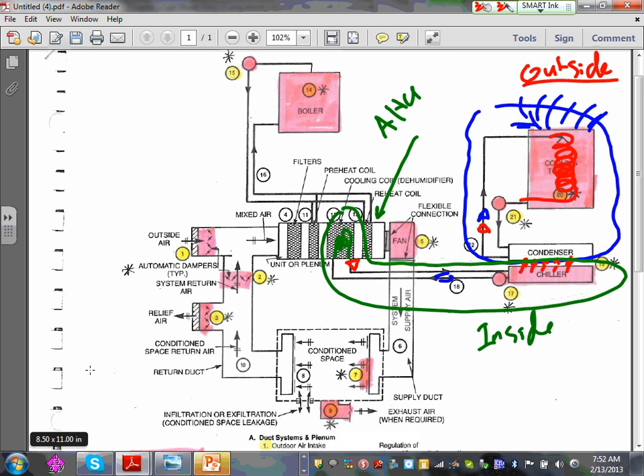Any comments, any questions? So here's your chiller. You can see that your chiller has two components in it, right? Everybody can see the chiller. Here's my chiller. One component goes between the chiller and the cooling tower. That's with the condenser. And the other one is from the chiller into the air handling unit. So these two pieces will typically be the same piece. Any comments, any questions? Two separate cycles.